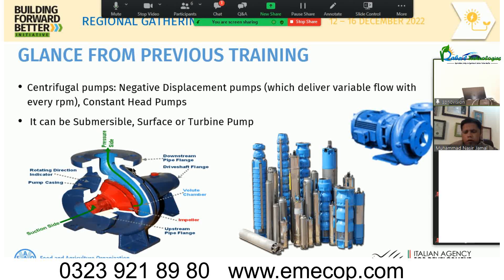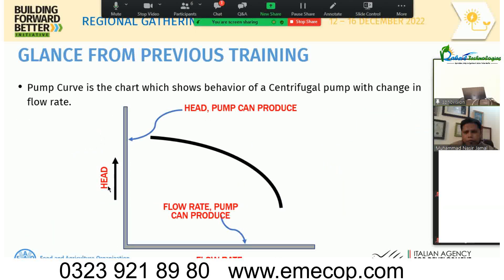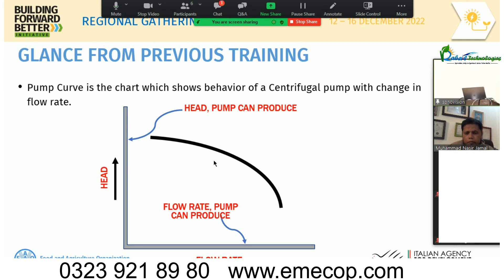This is a surface pump with a bare shaft because there is no motor or prime mover. Now, the pump curve — a very critical concept. A typical pump curve has flow rate on the x-axis and head on the y-axis, showing the relationship between head and flow at any particular operating point.